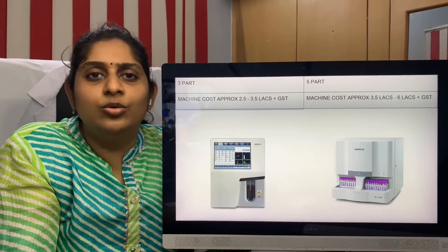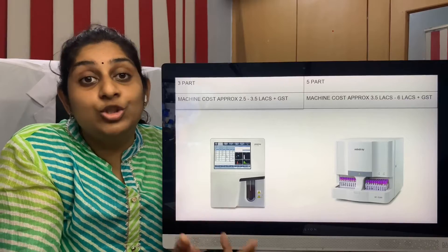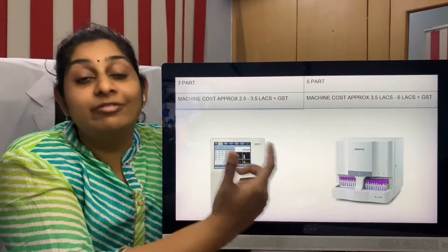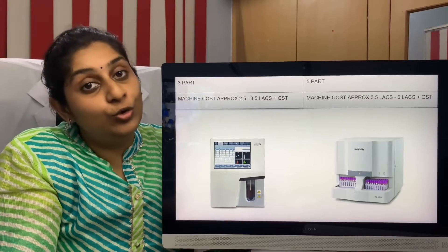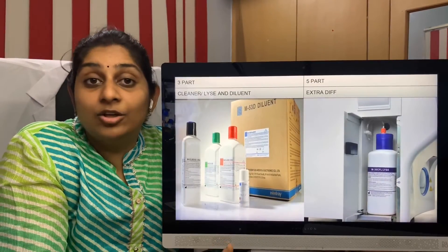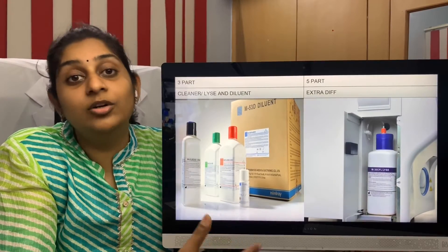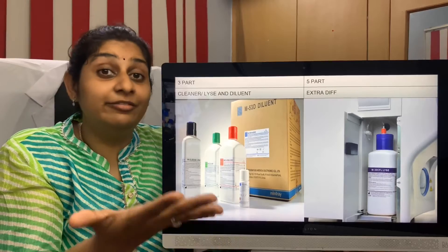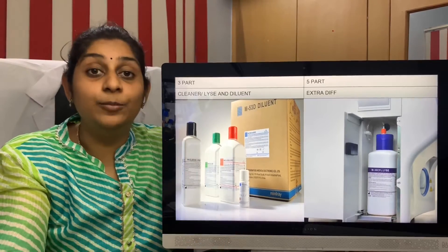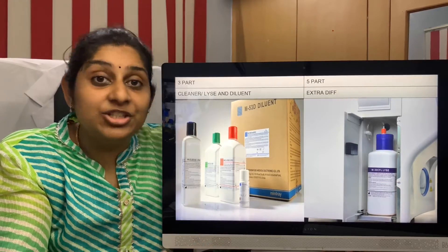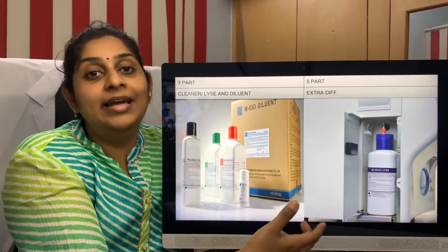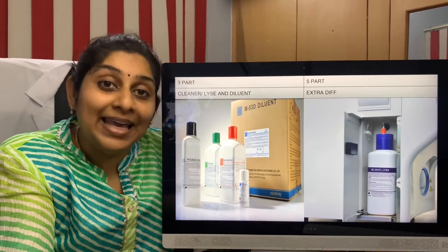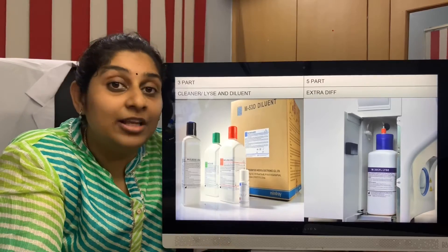What is the cost you need to invest for these cell counters? A three-part cell counter usually begins from around 2.5 lakhs and goes up to 3.5 lakhs. The difference between a three-part cell counter and a five-part cell counter is only about 2 to 2.5 lakhs at the maximum. Apart from the investment cost, we also have the running cost. In a three-part cell counter, we need a cleanser, lysing solution, and a diluent solution. In a five-part cell counter, it differentiates the WBCs into five parameters, so we also need a differential lyse solution, which means an extra cost of around 5,000 to 8,000 rupees on a bi-monthly basis.